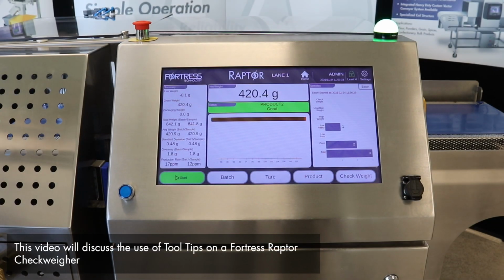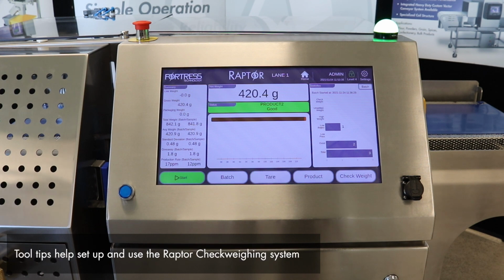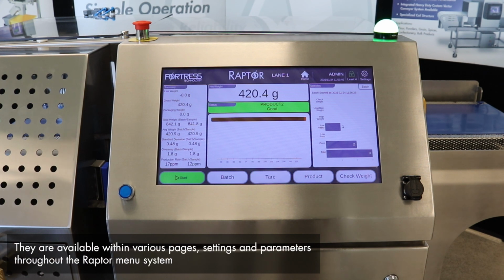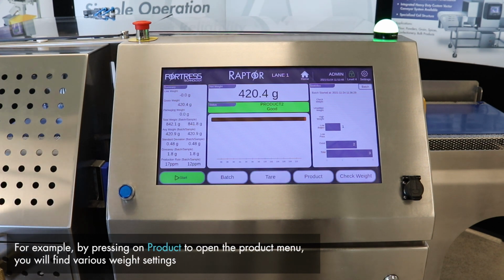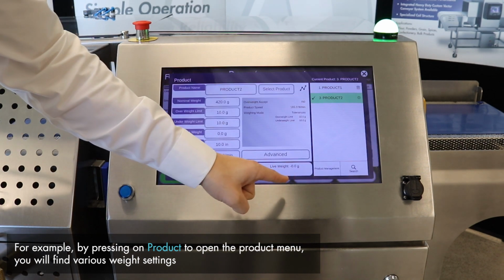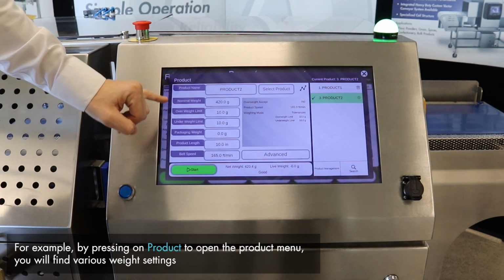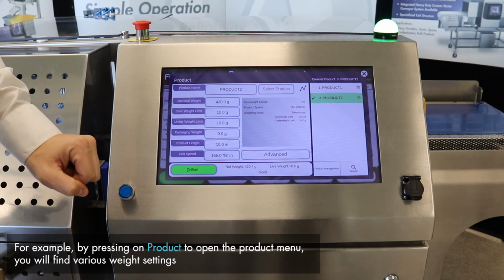Today we're going to look at tooltips on a Fortress Raptor checkweigher. Tooltips are an aid in setting up and operating the system and are available on various pages, settings, and parameters within the HMI. For example, in the product menu, we have various weight settings that initially come up.